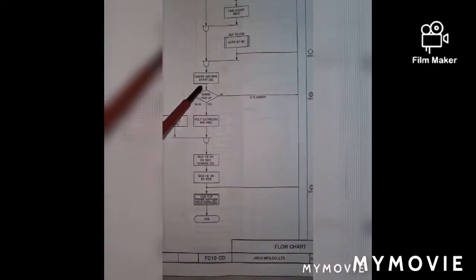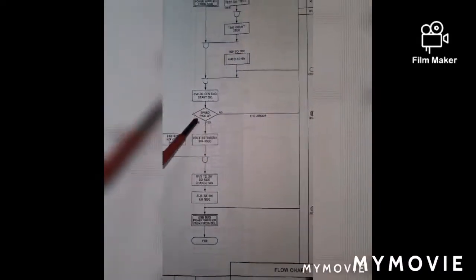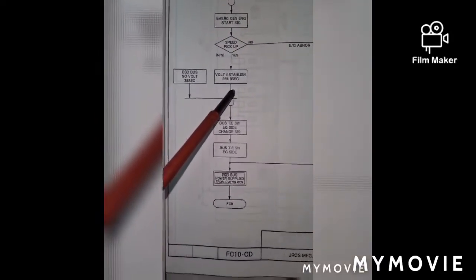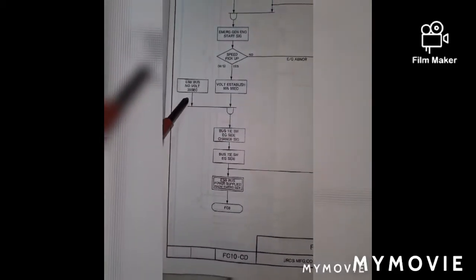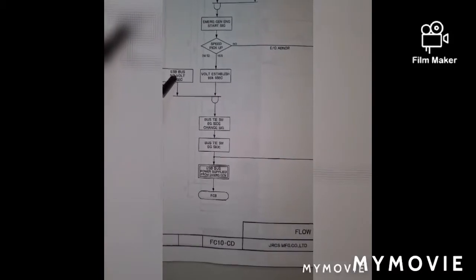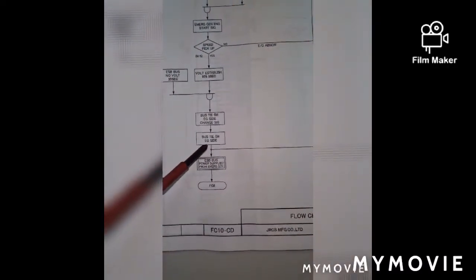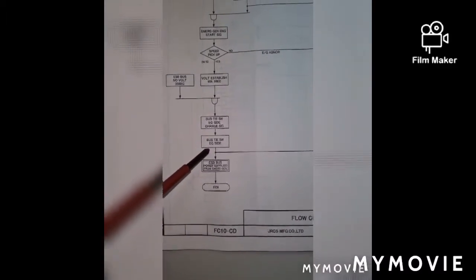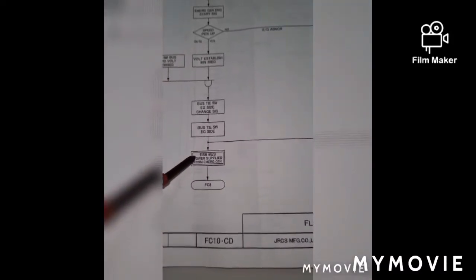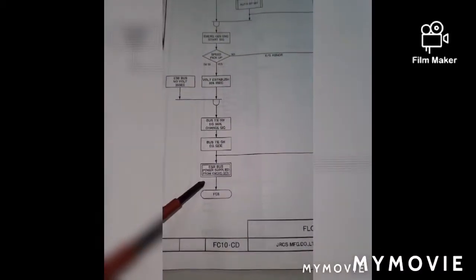Once the emergency generator has started and the speed is measured at about 1800 RPM, with volts at about 95% of the 450, it will take about 5 seconds. Then after 35 seconds, the emergency generator power will be supplied to the emergency switchboard. Then you need to put the changeover switch on the emergency generator side. Put the changeover switch on the emergency generator side. Then you will now have the power from the emergency generator when the changeover switch is connected.